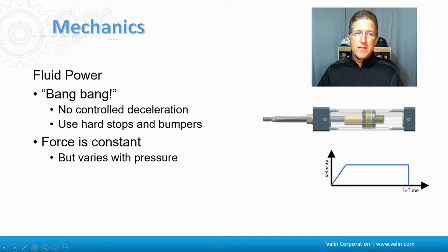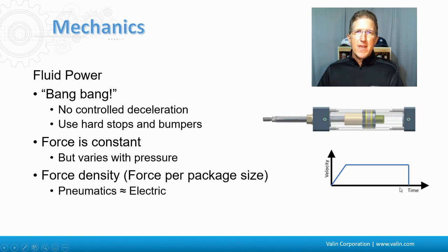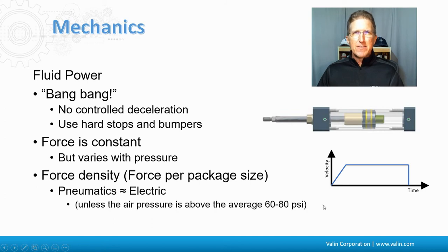The force is constant, which is what causes that acceleration, but it varies with the pressure. So if you need a certain amount of force at 60 psi and you only have 50 psi, you don't get as much force as you'd want. The force density is sometimes important when talking about fluid power. I call it force density because it's the amount of force you get out of the package size of the actuator itself. Pneumatics and electric are about the same. In the usual 60-80 house psi, I have seen applications where someone's using 100 psi on an actuator, and the pneumatics can get a little bit more out of its force density. But usually the average is in that 60-80, and it makes them about the same.